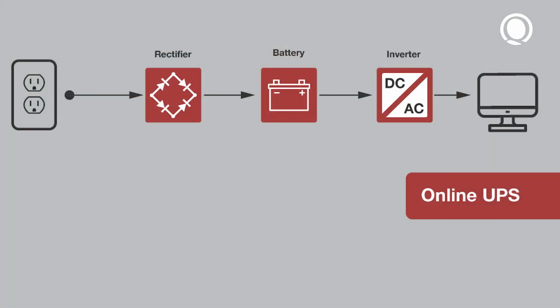The next type of UPS, which is typically found backing up servers, critical equipment, and always typically in a data center, is an online double conversion UPS, also just sometimes called an online UPS. What it does is it brings in line from the utility, plugs into the wall, in other words, or some fancy type of jack if it's in a data center, goes into a rectifier, goes into a charger, charges the battery. The battery gives us our DC output, and that goes into an inverter. And the inverters on these guys are very, very pure sine wave, clean output devices, and that drives your equipment.